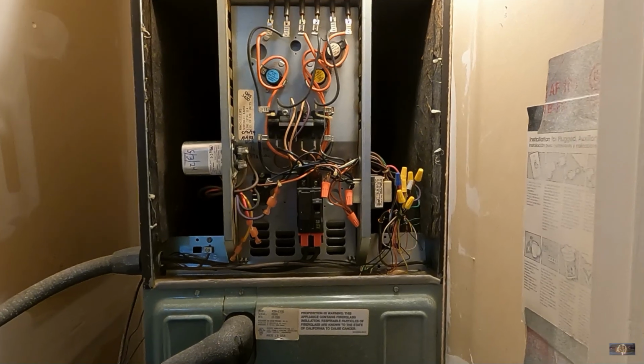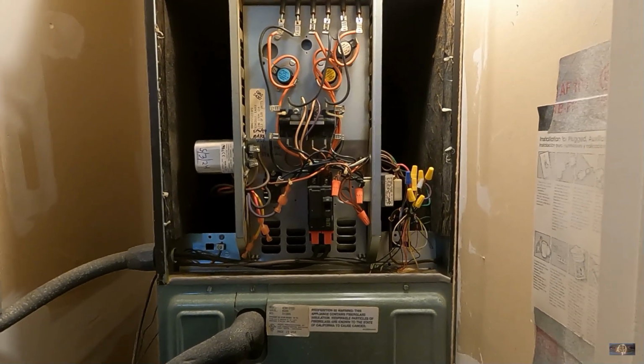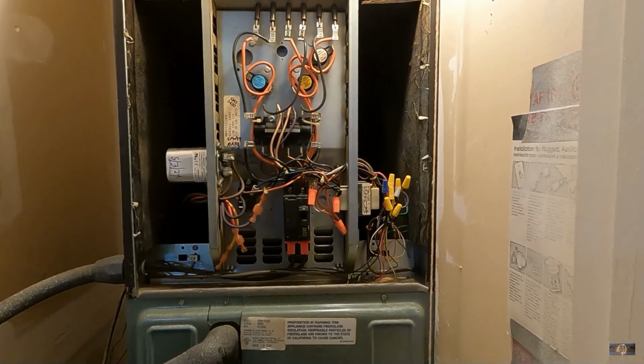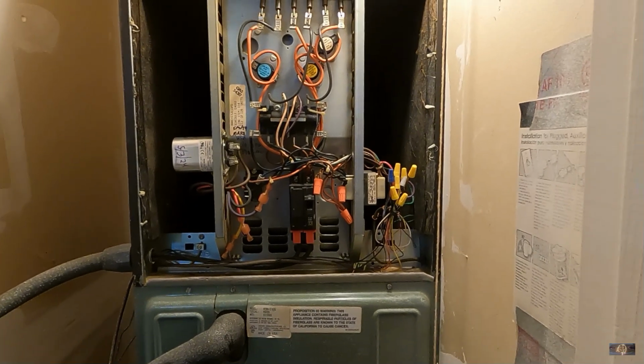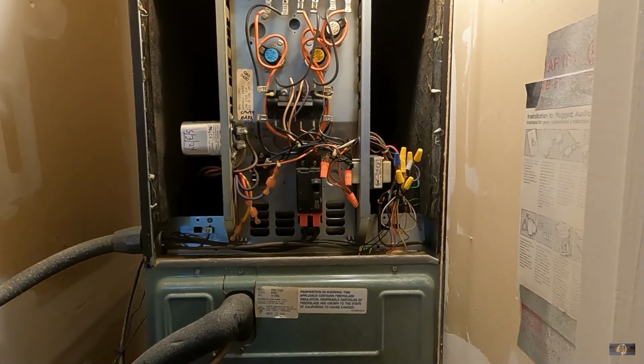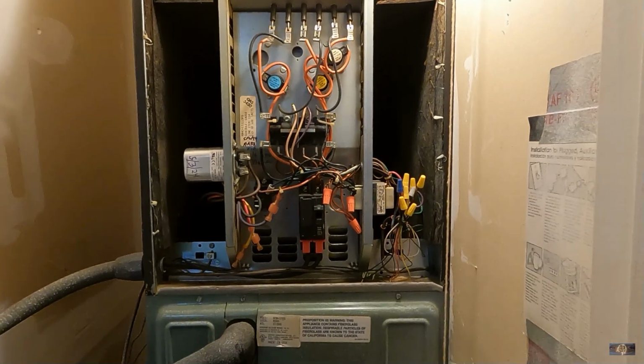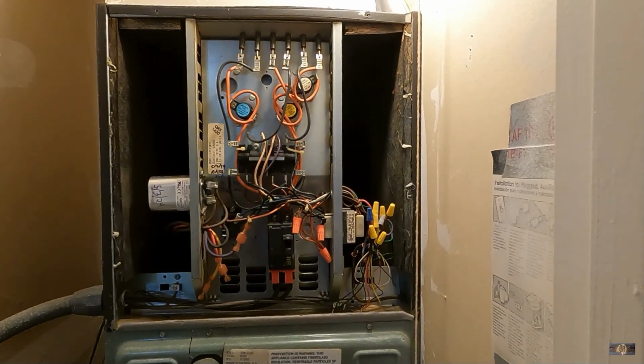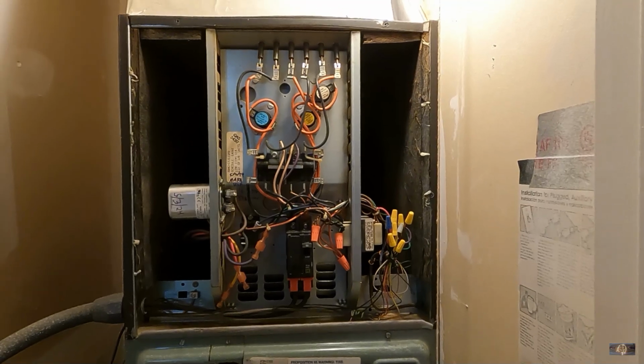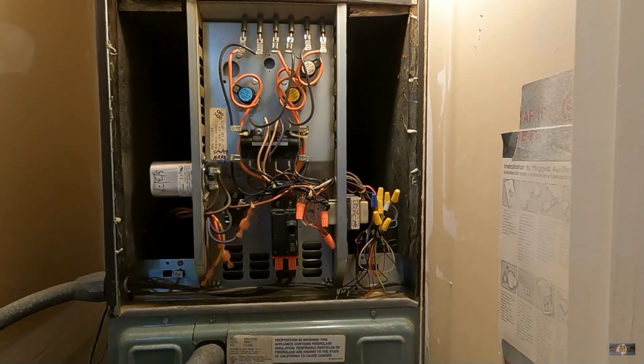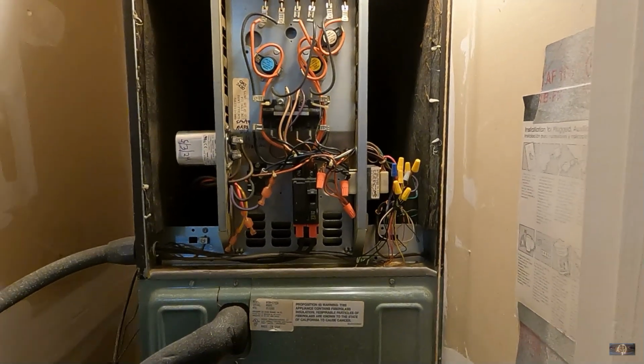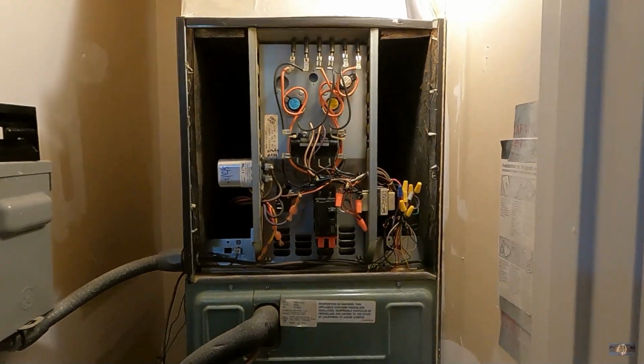It's really important after you're done with the maintenance to always do a test out. Check your temperature split, check your pressures, check your superheat and subcooling, and make sure the system's operating well after you touch it. One mistake, and if you have to go back for free, or if you work for somebody, they're going to be pretty upset with you. So always check the system before you leave, make sure it's working.